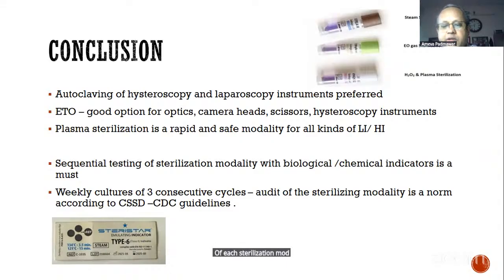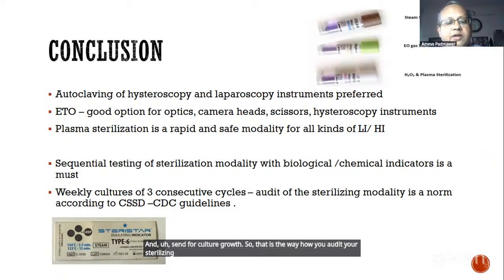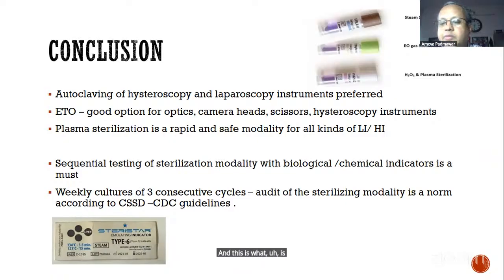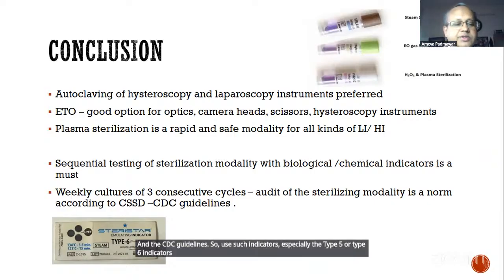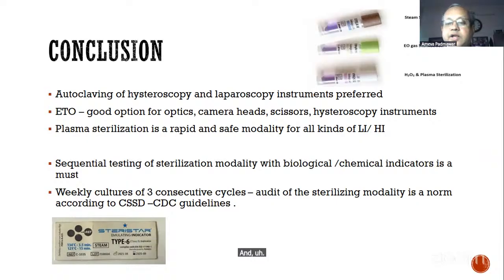Mind you, before I conclude the discussion, you have to check the validity of each sterilization modality. Okay, so you have to use a biological or a chemical indicator at a fixed time based on the protocol which you're following. So the sequential testing of the sterilization cycles is to be checked. Weekly cultures of 3 consecutive cycles are to be used and sent for culture growth. So that is the way you audit your sterilizing modality. And this is what is followed by most of the CSSD and the CDC guidelines. So use such indicators, especially the type 5 or type 6 indicators. And biological indicators, of course, you have to send them for culture at the end of it.